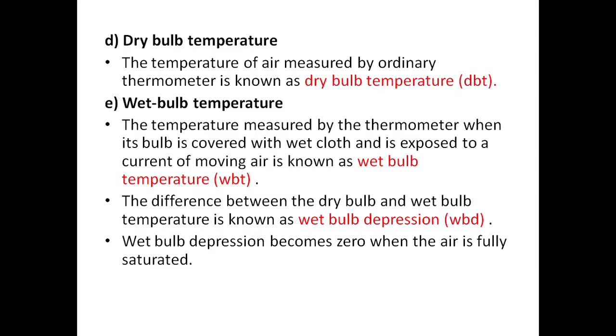When the wet cloth is wrapped around the thermometer, it removes heat from the air and decreases the temperature recorded, because water in the cloth is evaporating and takes up heat as latent heat — changing phase from liquid to vapor. When air is fully saturated, no evaporation occurs, so wet bulb depression becomes zero and DBT equals WBT.